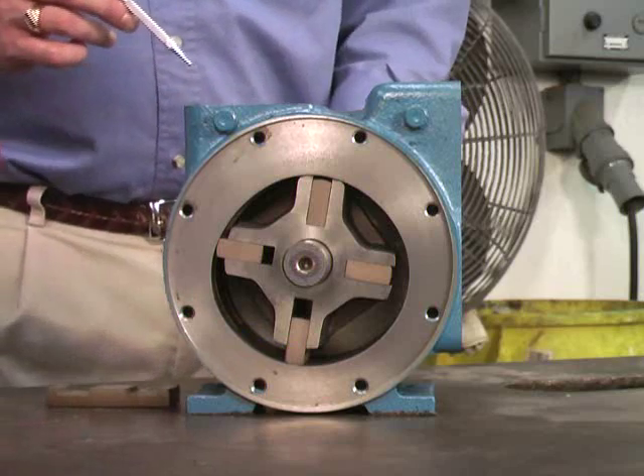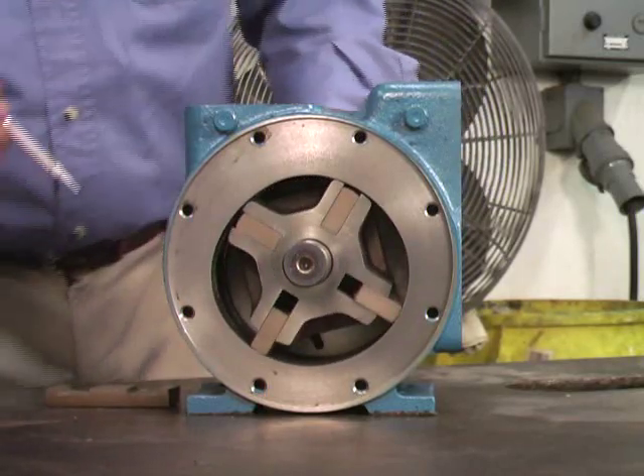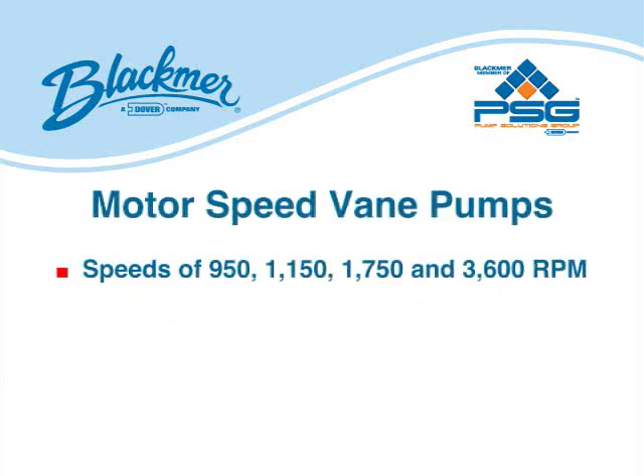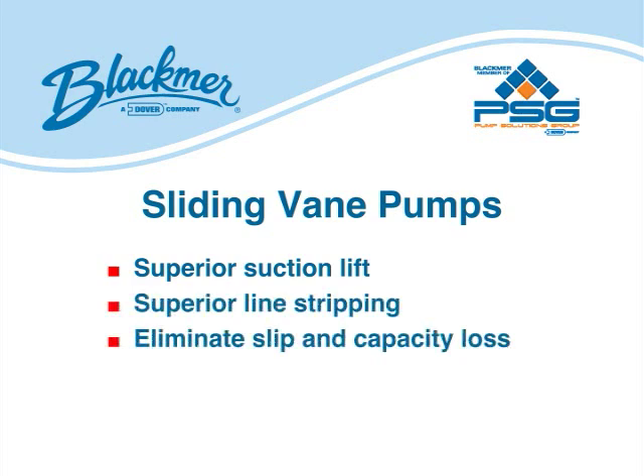Sliding vane pumps are exceptional for thin liquids, but as this brief demonstration illustrates, they are also excellent for moving thick liquids, particularly when operating at slow speeds. Standard vane pumps are available in speeds of 100 to 1200 RPM. Motor speed models run at various speeds — 950, 1150, 1750, and 3600 RPM — and pressure ranges from 125 to 200 PSI. Sliding vane pumps offer superior suction lift and line stripping capabilities. Their self-adjusting vanes eliminate energy-robbing slip and capacity loss associated with gear and lobe pumps.